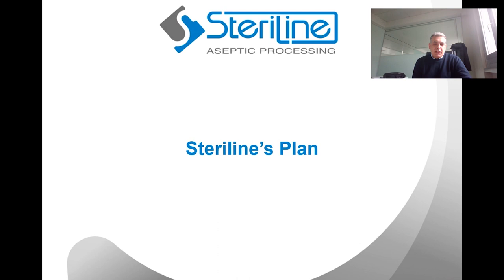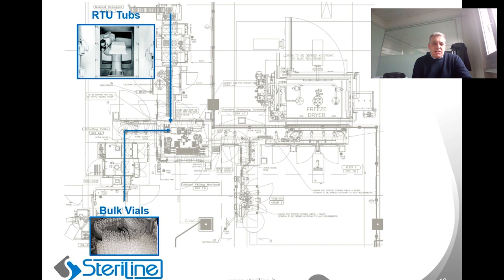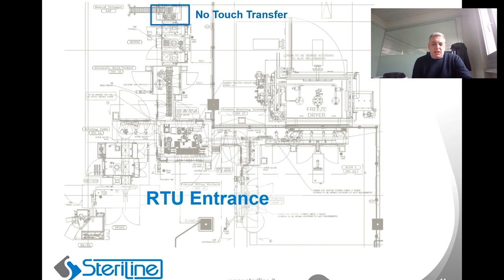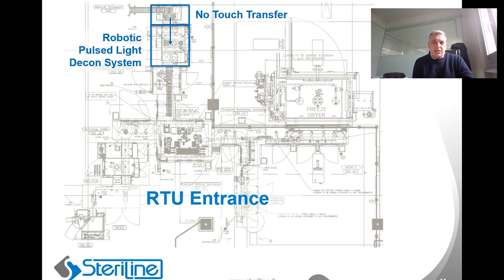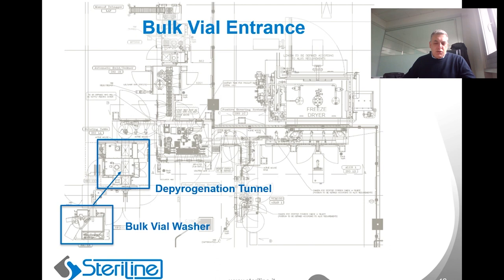We would first create a separate entrance for bulk vials and RTU containers that meet at right angles of the filling machine isolator. The RTU entrance will contain a no-touch transfer that feeds the tub to the Steriline Pulse Light sterilizer that sterilizes the surface of the tubs by means of Pulse Light made by Claranor. The outlet of this isolator goes to a robotic delid/deliner machine that feeds the filling machine. The bulk vials come through a washing machine that goes into a depyrogenation tunnel, and out of the sterilization tunnel there is a turntable isolator which feeds the scroll used by the robot to fill the filling machine.